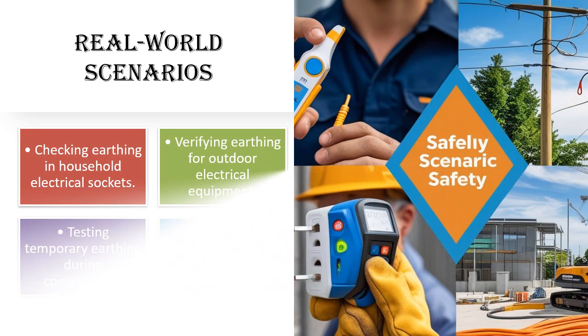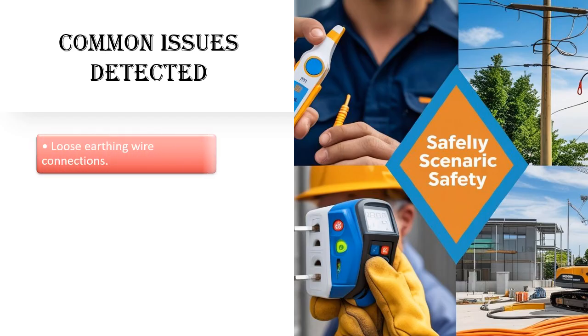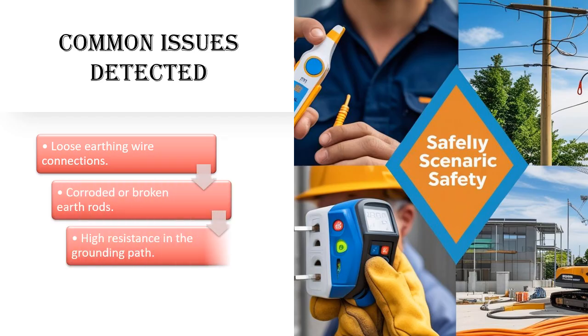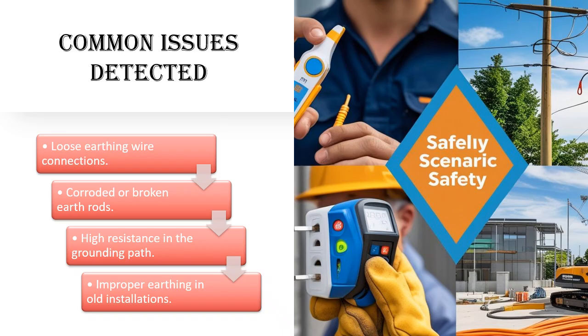Common issues detected. Some common issues that testing can reveal include loose earthing wires, corroded or broken rods, high resistance in the grounding path, or poor earthing in older electrical systems. Identifying these problems early can prevent accidents and damage.